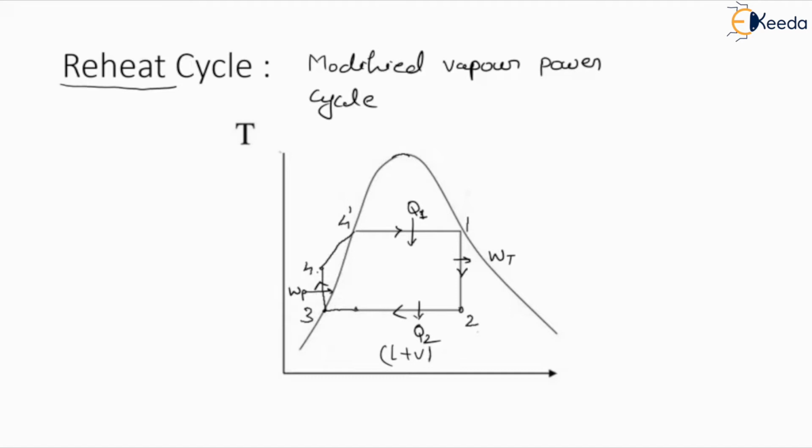This was the drawback when we transfer liquid plus vapor: we are not able to attain the exact boiler pressure which we require. So to get the required boiler pressure, we convert this liquid plus vapor into saturated liquid, and we can easily transfer this liquid to the boiler with proper boiler pressure.